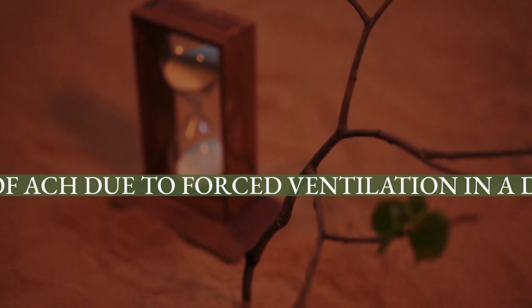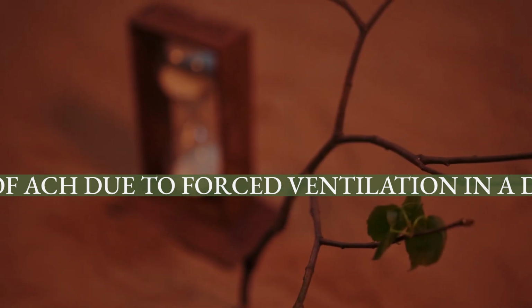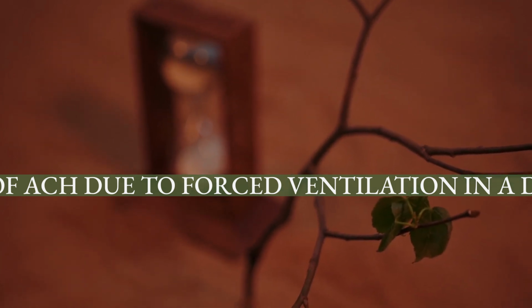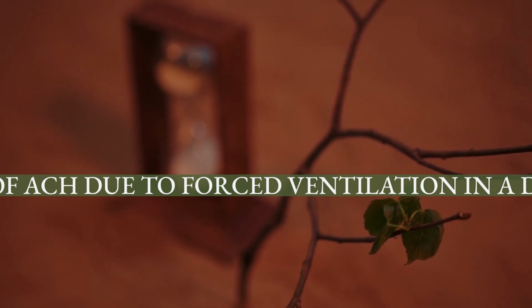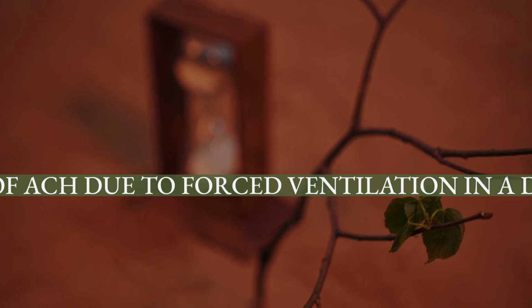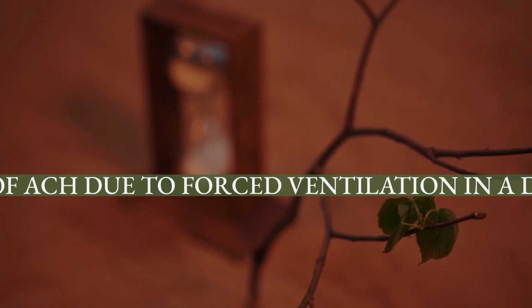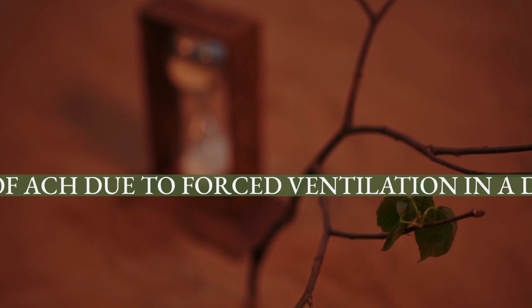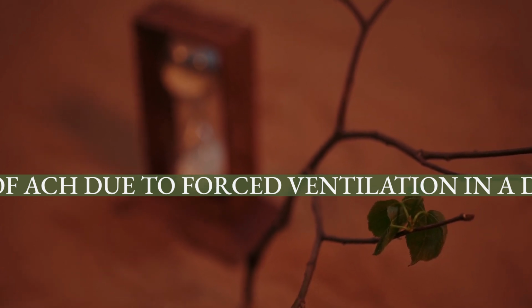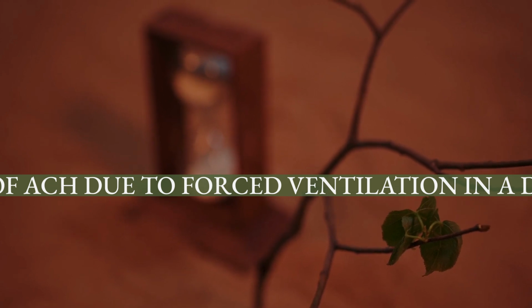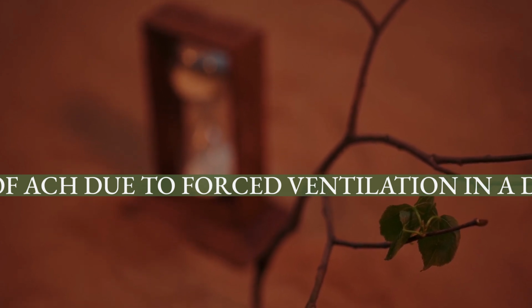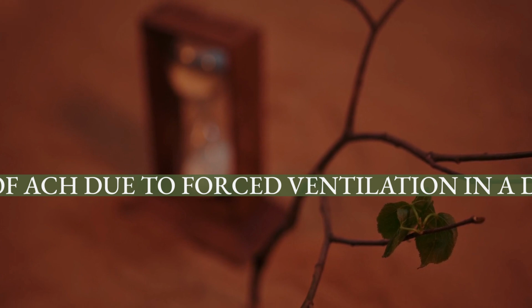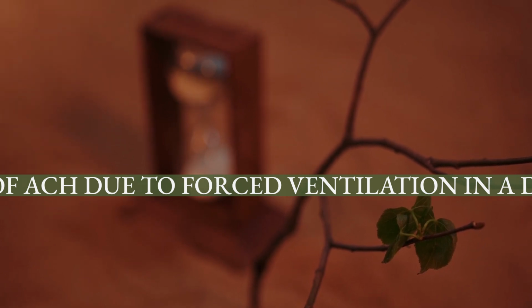Air changes are often cited as a means of preventing condensation in houses with forced ventilation systems, often rated in ACPH though without referencing the size of the house. However, where ACPH is already greater than 0.75, a forced ventilation system is unlikely to be of use at controlling condensation, and instead insulation or heating are better remedies.